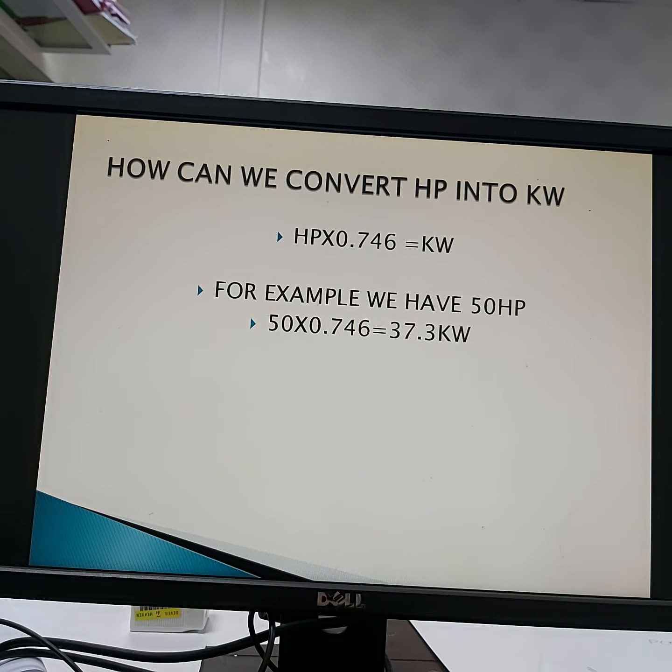So if you are going to design or work in a factory, you must know how to convert HP power into kilowatt, and this is very simple. Multiply 0.746 with horsepower, you will get kilowatt power.